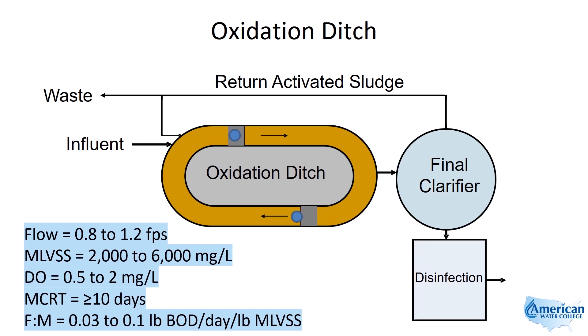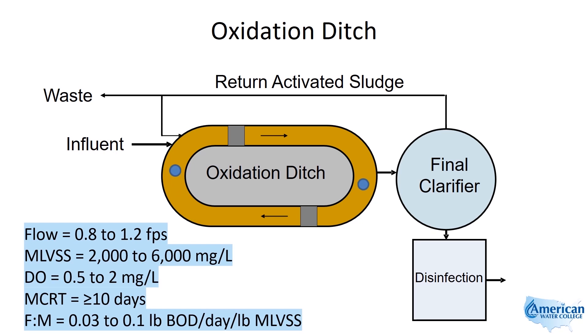Any time an adjustment is made, the operator should allow several days for the process to stabilize before making an additional change. The mixed liquor in the oxidation ditch should have a medium to dark brown color. Typically, the sludge age is greater than 10 days, and the system operates with a very low F to M ratio in the range of 0.03 to 0.1 pounds of BOD per day per pound of mixed liquor volatile suspended solids. This makes it a very stable process.